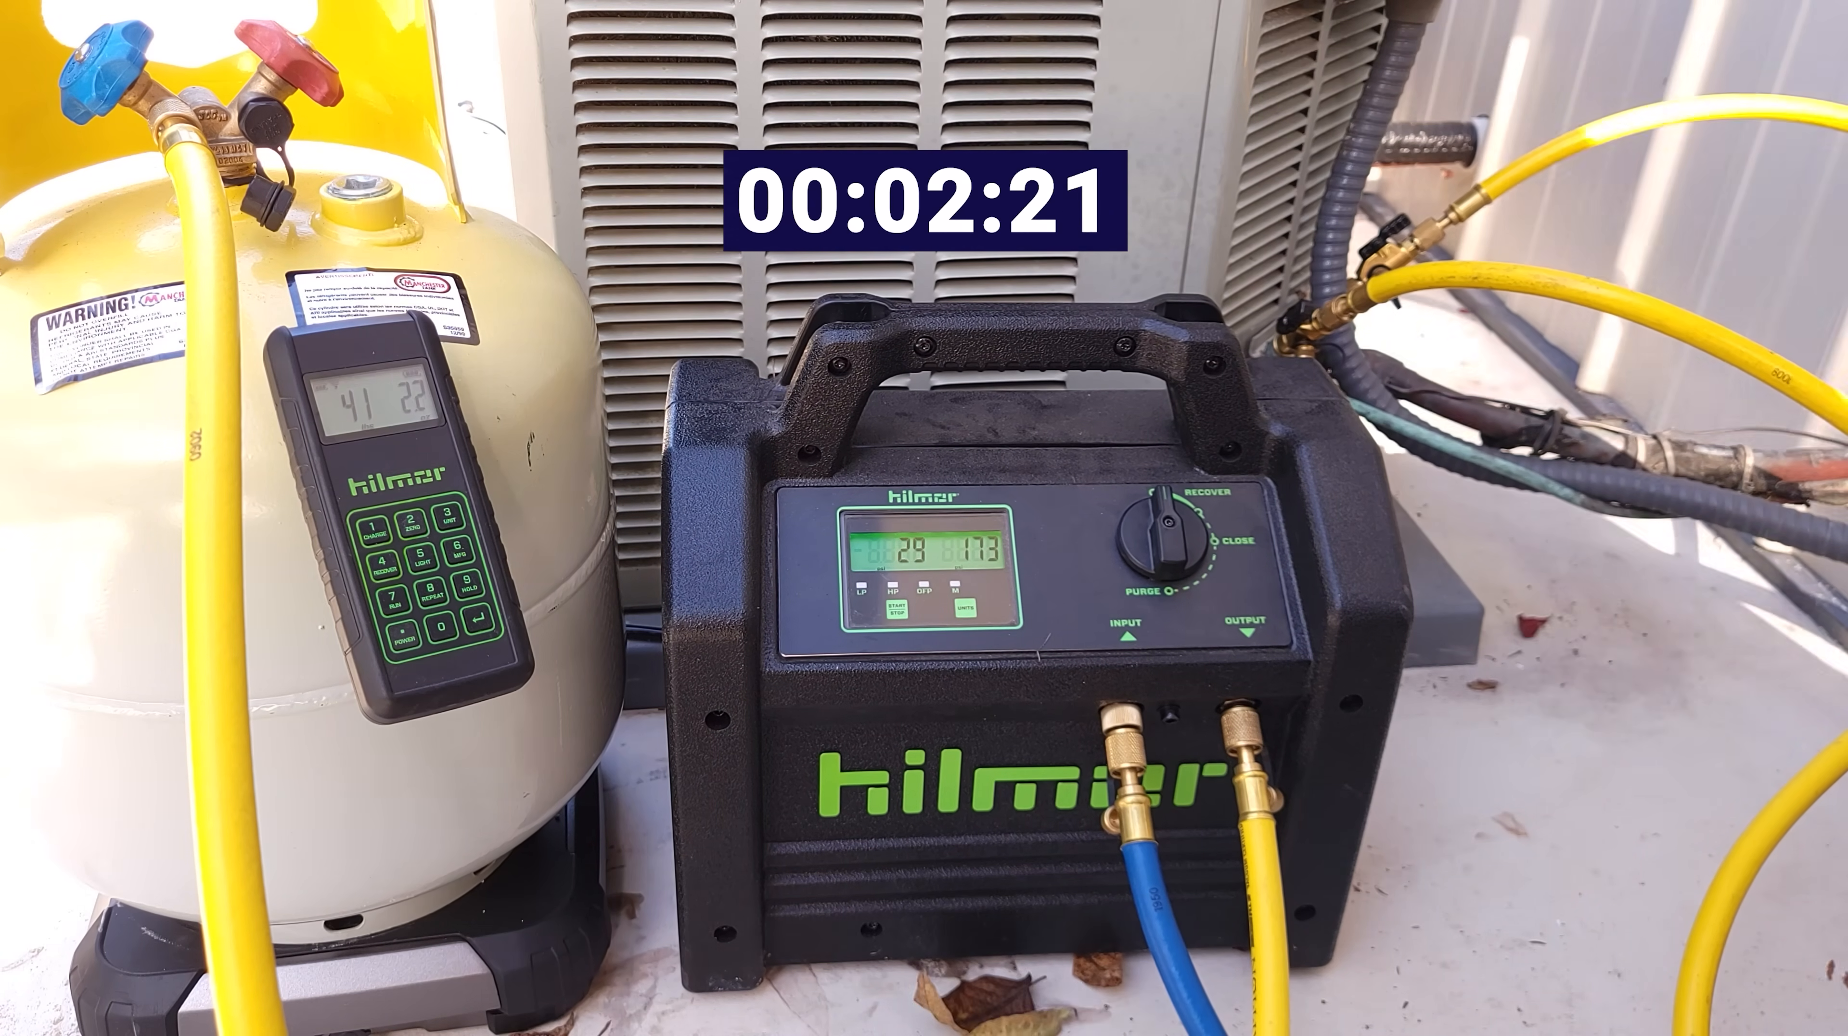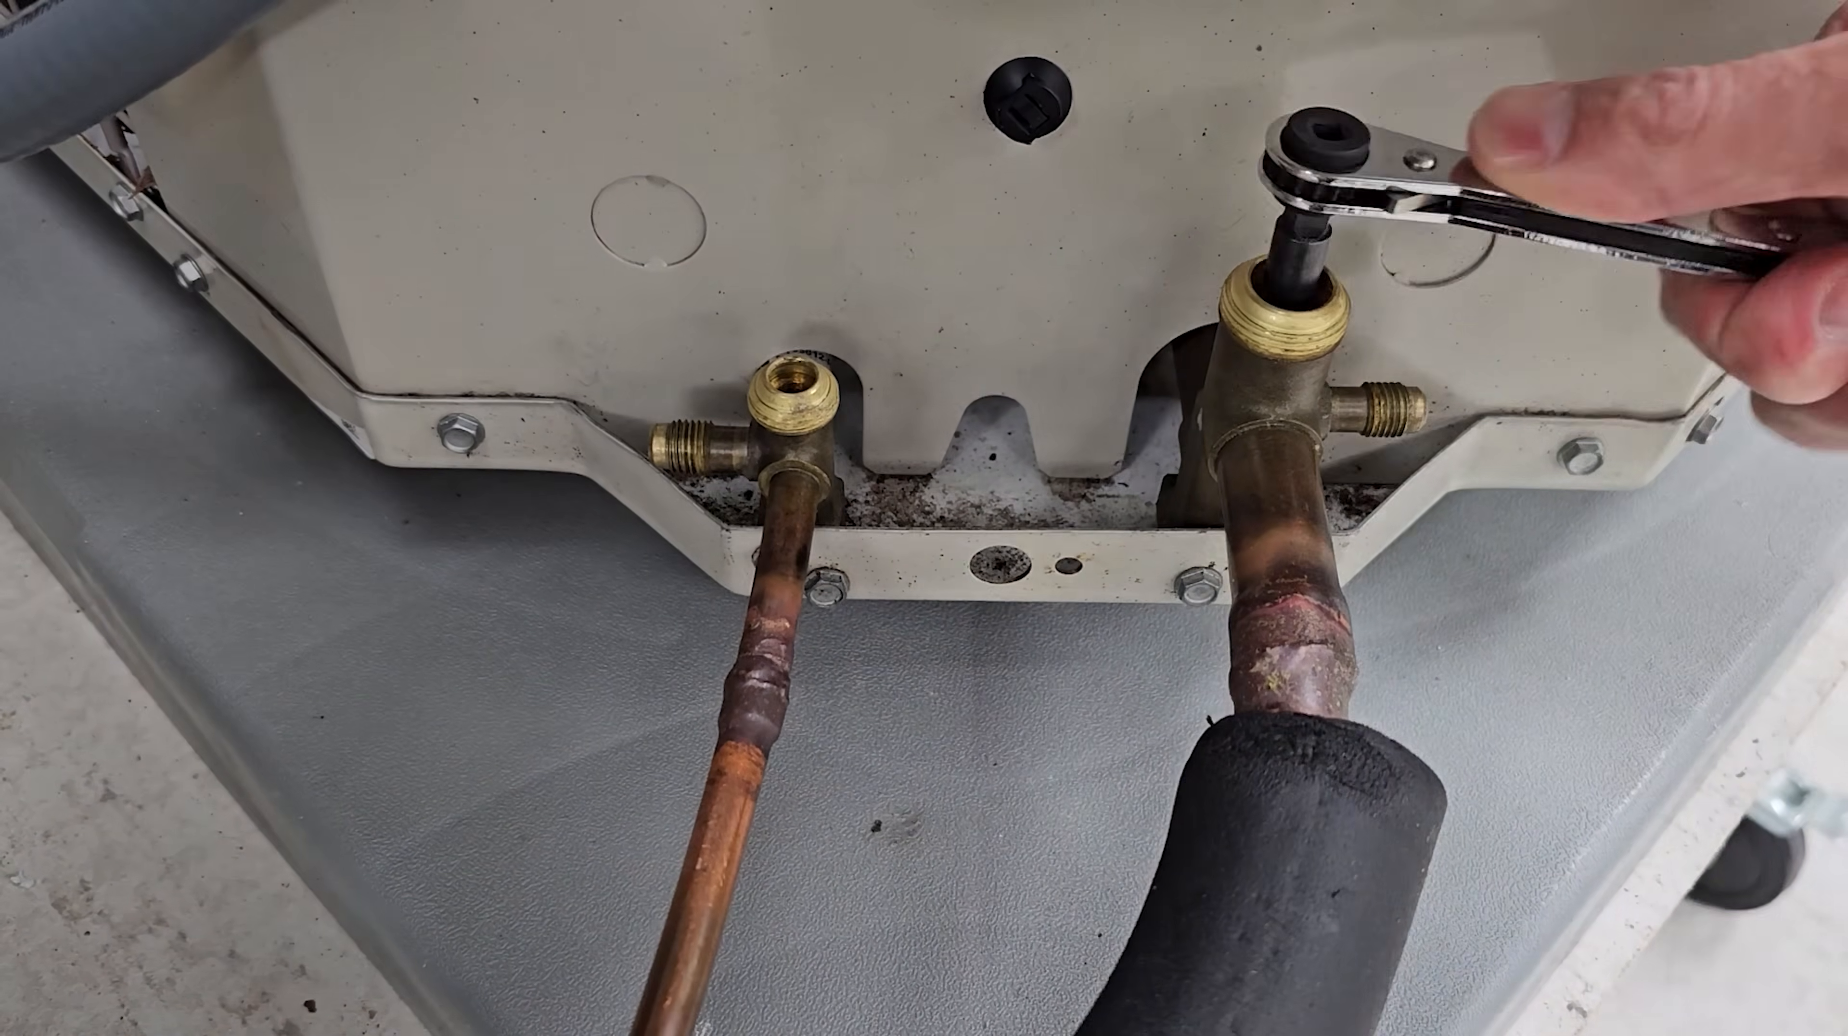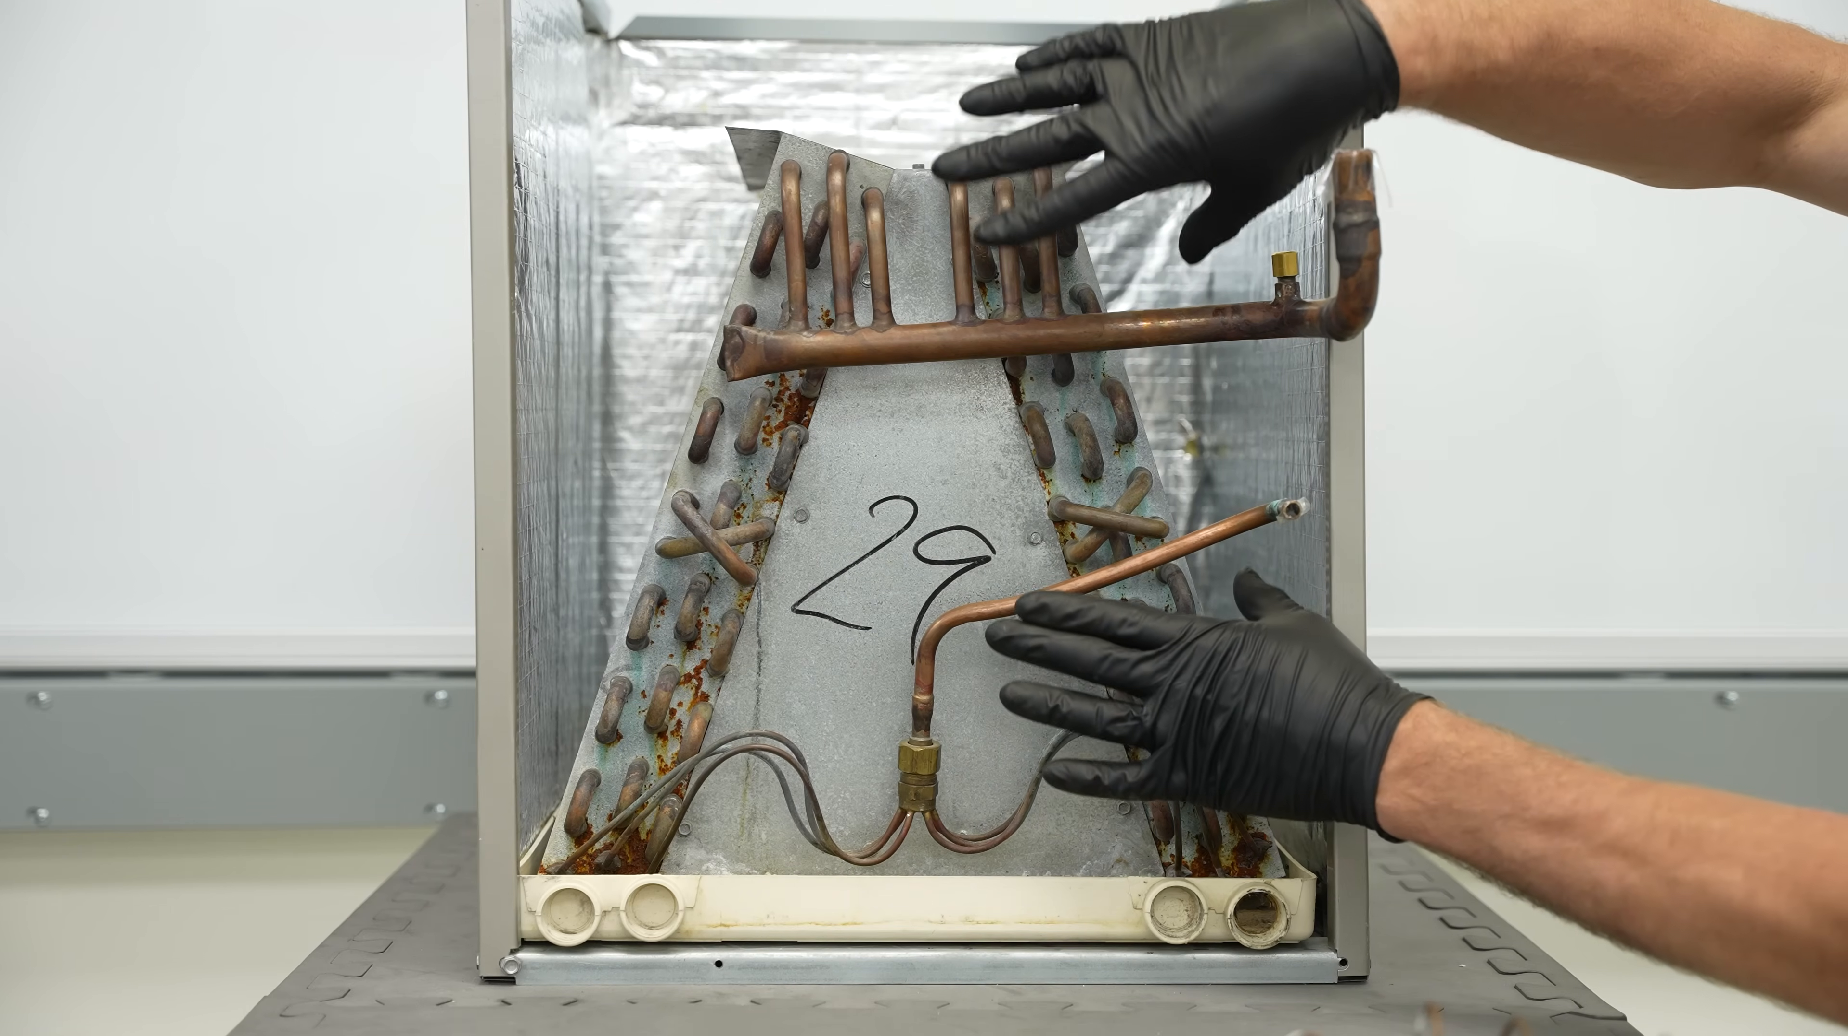Or what you can do is, with the power off, shut the liquid line and the vapor line service valves and just recover the refrigerant in the line set connecting to this coil and the refrigerant in the coil itself.